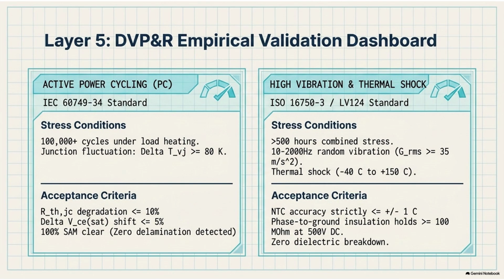60749-34 standard. What are they doing to the module here? This test aims to find the true structural fatigue limit of the module's materials. They place the controller on a test bench and forcefully push massive, continuous pulses of load current through the silicon chips. The goal is to rapidly heat the chips up, intentionally forcing a massive temperature fluctuation, a delta T. A thermal swing. Yes, and they mandate a delta T of at least 80 Kelvin, often pushing it to a 100 Kelvin swing. So they violently heat the chips up, turn the power off, and blast it with cold water to crash the temperature, and then immediately heat it up again, over and over.